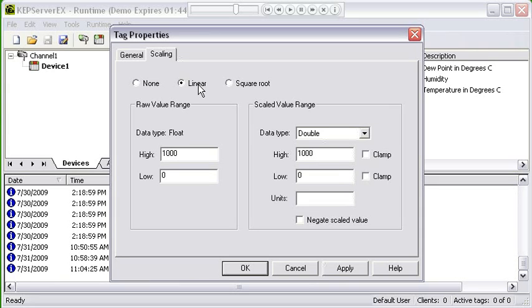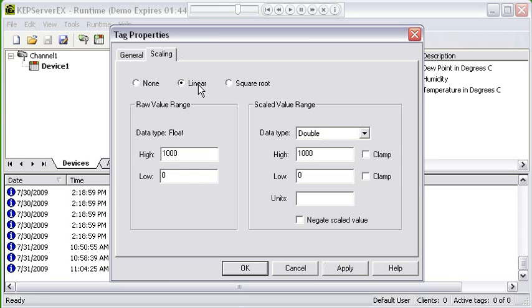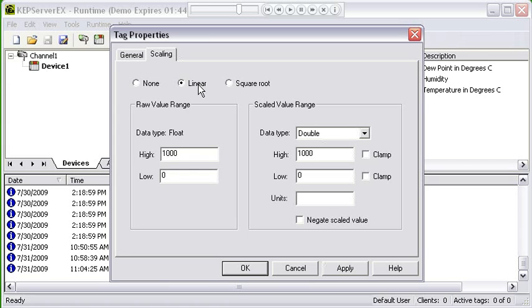You see that a lot with small PID controllers and things where they'll have a temperature that they're showing on their faceplate which might say 70.3, and when they send that data to a server like ours, it would show us 703 because it's sending in integer format and we have to scale that. You would set your high and low scale value, the raw value, and you would set your high and low scale value for the scaled side, and then that scaling would be done so you had your true temperature value.